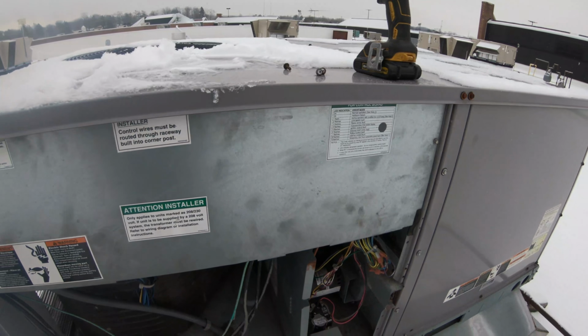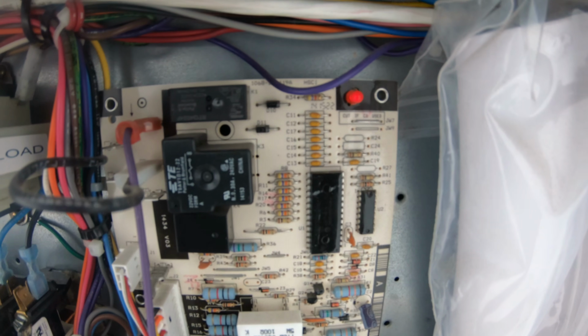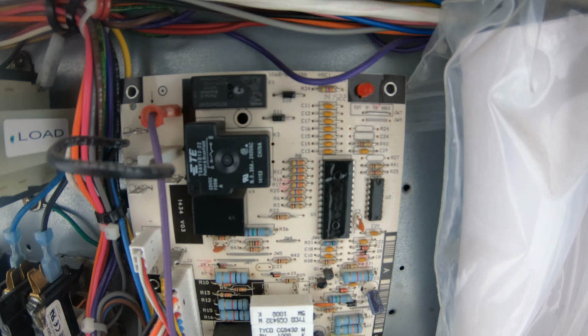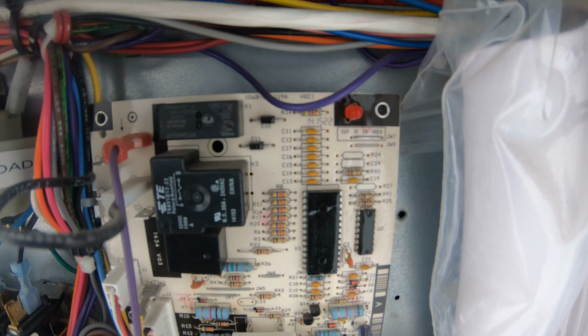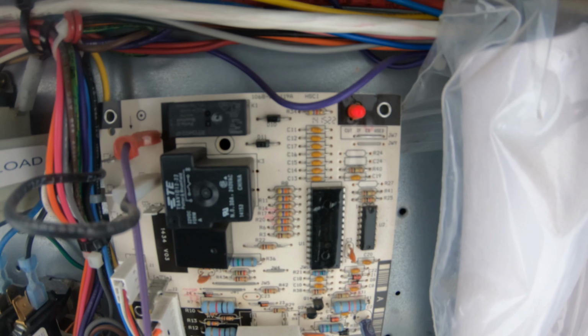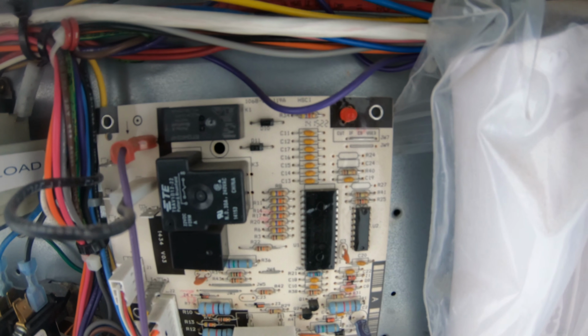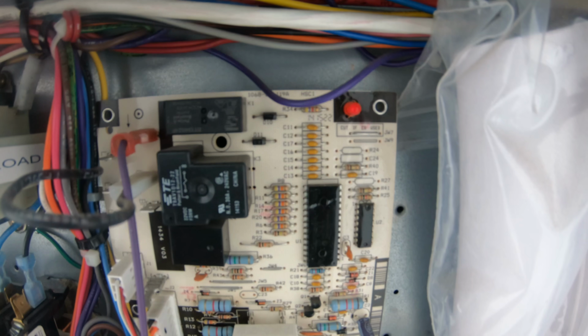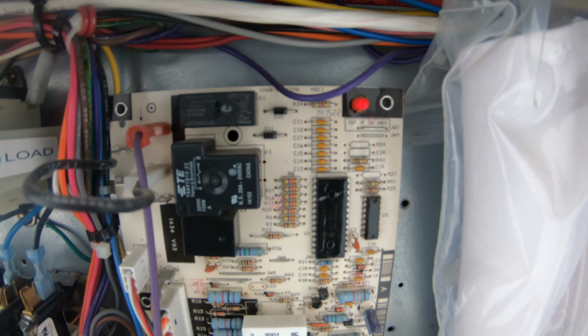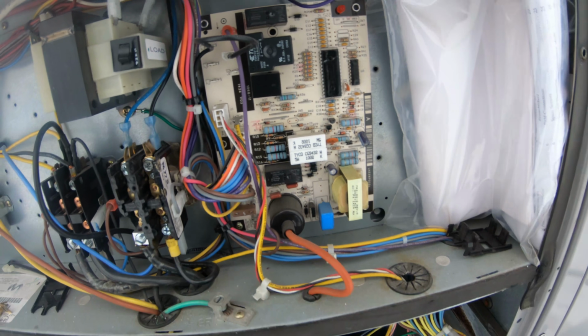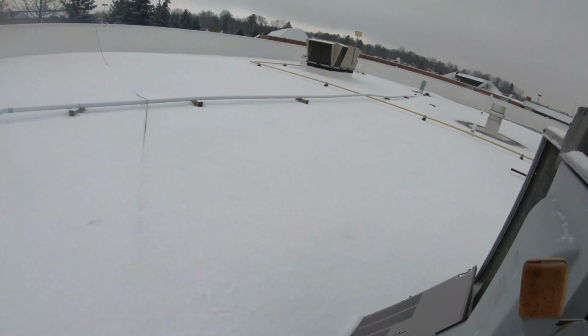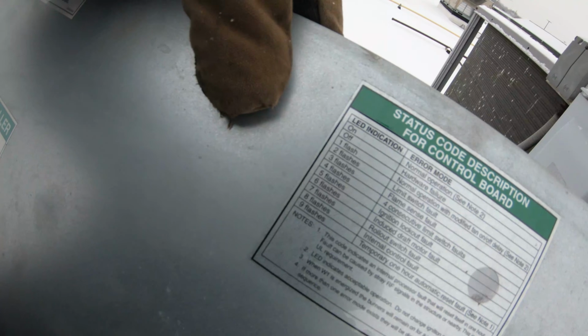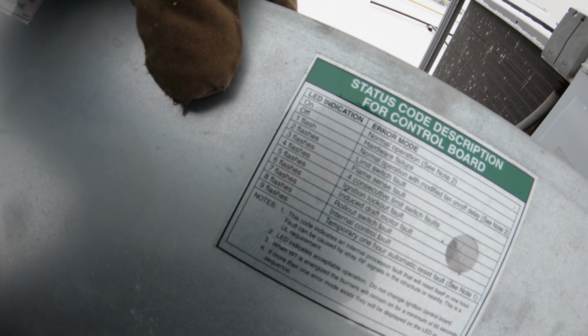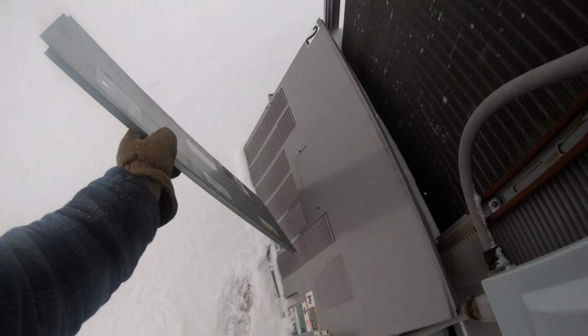Let's see what kind of indicator light we've got going on here. 1, 2, 3, 4, 5. Let's check it again. 1, 2, 3, 4, 5, 6, 7, 8. So we get 2 different flashes: 5, ignition lockout fault, and 8, internal control fault.